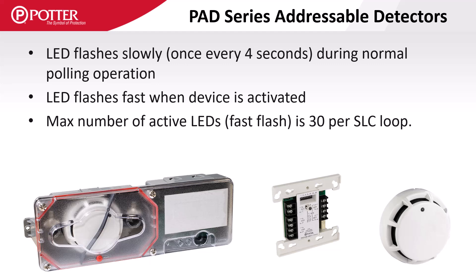Some operating characteristics of PAD devices are that the LEDs flash approximately once every 4 seconds while the SLC polls the circuit, and the device LEDs do not latch on when activated, but instead flash rapidly. Each SLC loop can only have a total of 30 LEDs activated in rapid flash mode at a time, but that doesn't stop the control panel from receiving additional events.